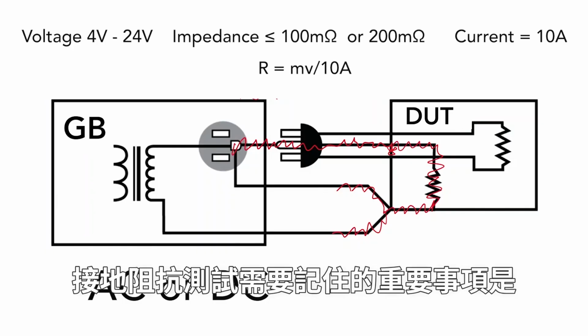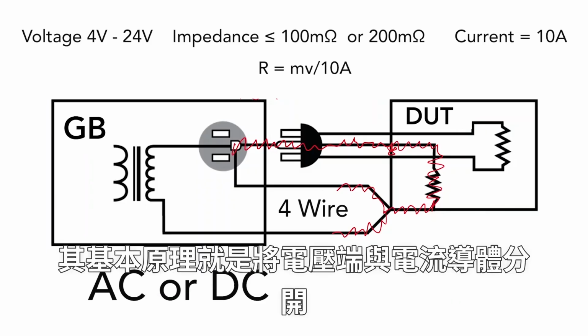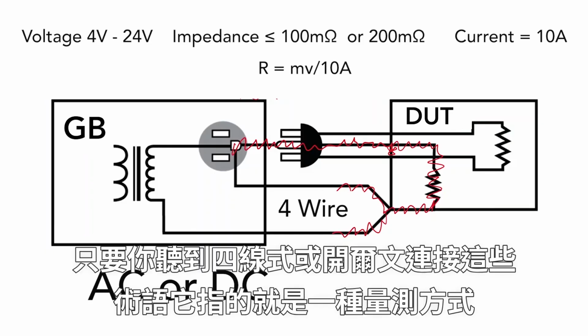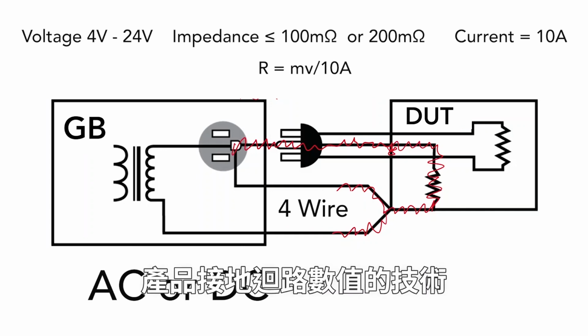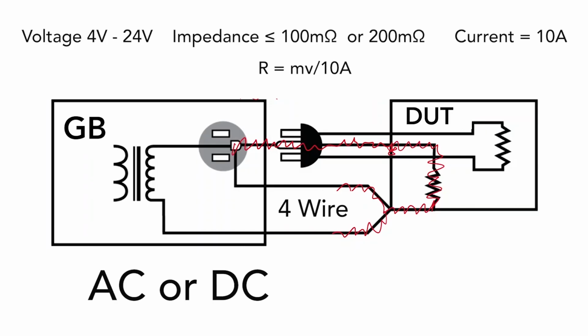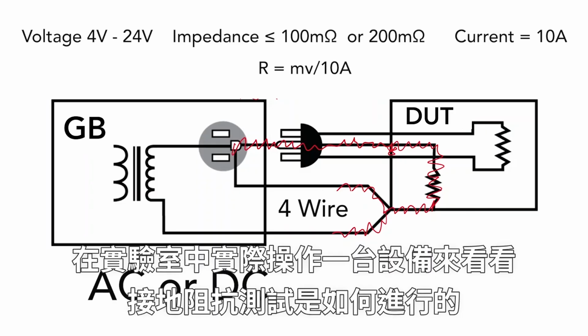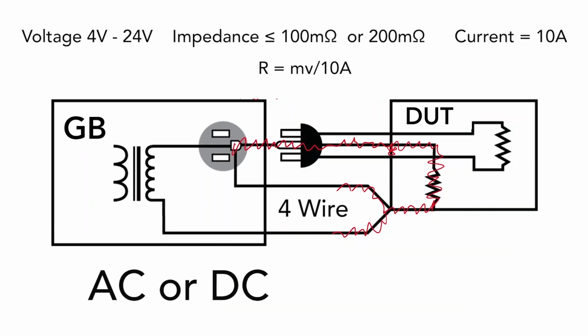And another important thing to remember about the ground bond test is that some ground bond testers utilize a 4-wire measurement technique, which is basically separating the voltage and the current conductors to get a more accurate reading. So anytime you hear the term 4-wire or Kelvin connection, it's just a measurement technique that allows you to measure a more accurate value of the product's ground circuit. Next, we will take a look at the ground bond test being performed on an actual device in our lab.